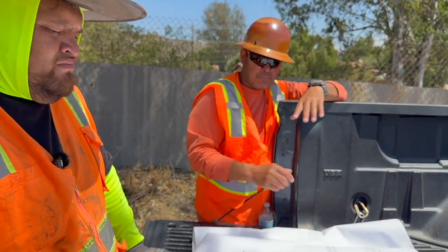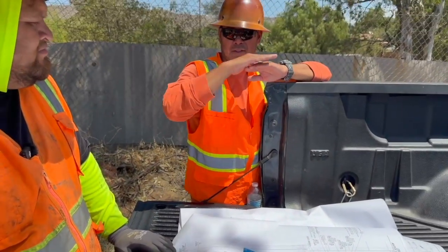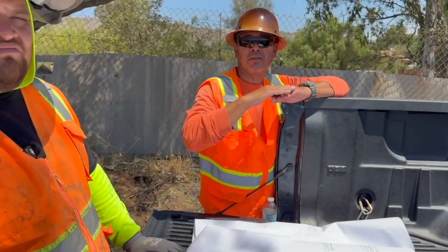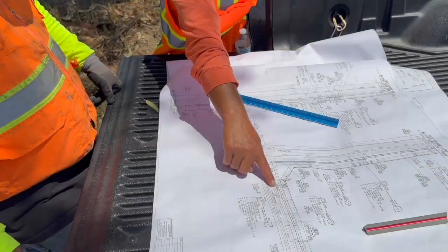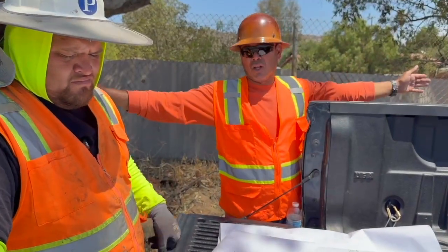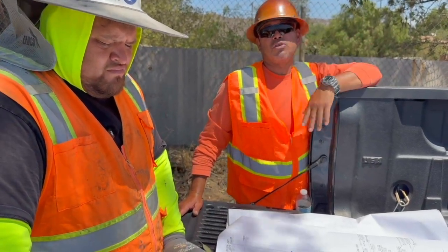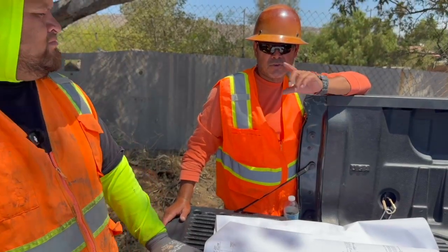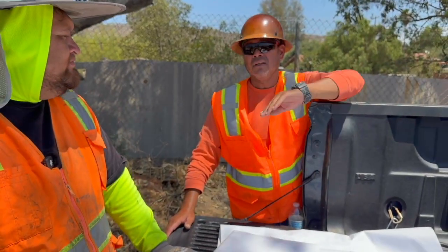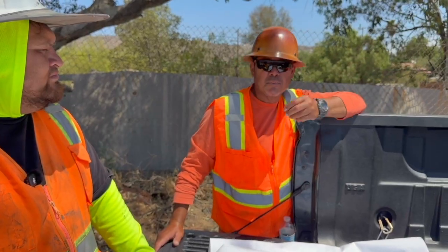This one right here is a structure that is going to have a transformer pad on top, so that has to be level. When I say level, it's 100% level. For the distance of the box, that is 15 feet tall outside, 15 foot long outside, you have a 1/4 inch max decline that you can miss. 1/4 inch for 15 feet. So that means it has to be perfect, because when you put 15 feet on a level, 1/4 inch pretty much doesn't exist. Yeah. So it has to be 100% level.